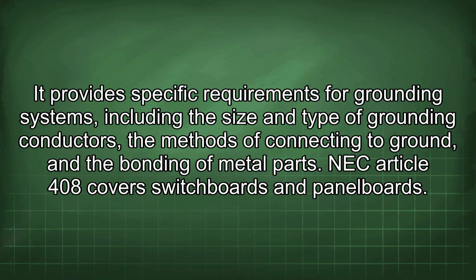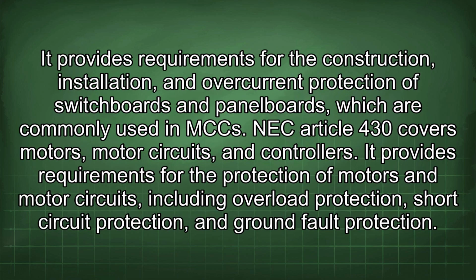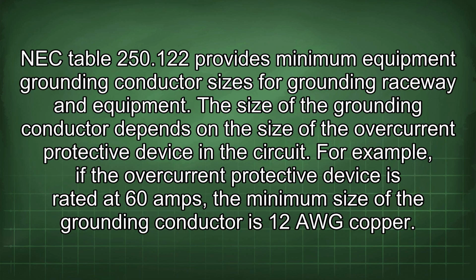NEC Article 408 covers switchboards and panel boards. It provides requirements for the construction, installation, and overcurrent protection of switchboards and panel boards, which are commonly used in MCC. NEC Article 430 covers motors, motor circuits, and controllers. It provides requirements for the protection of motors and motor circuits, including overload protection, short circuit protection, and ground fault protection.